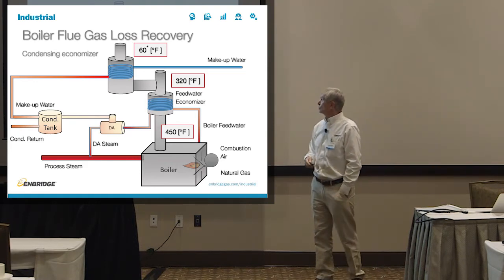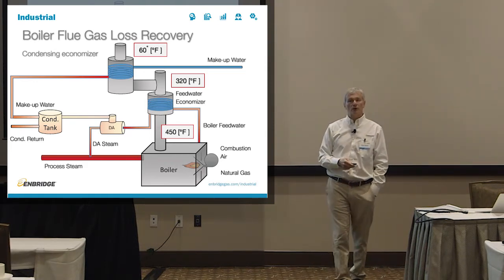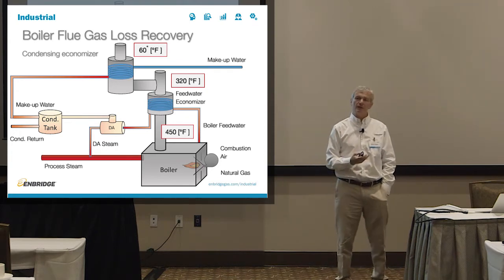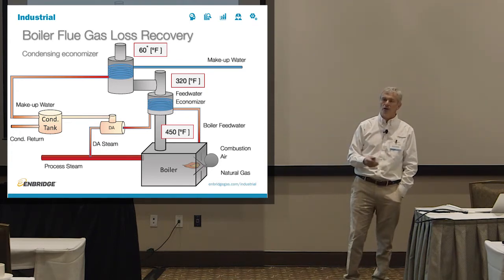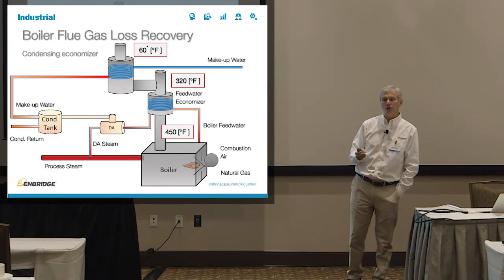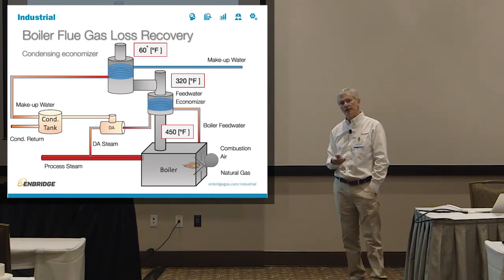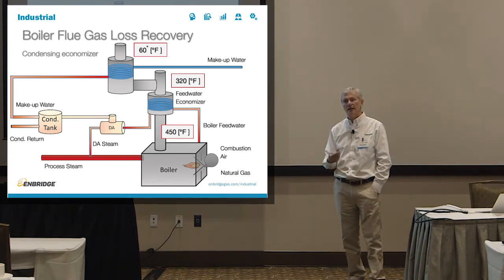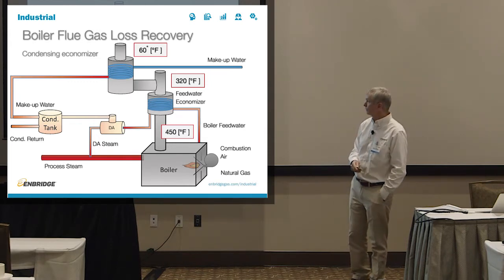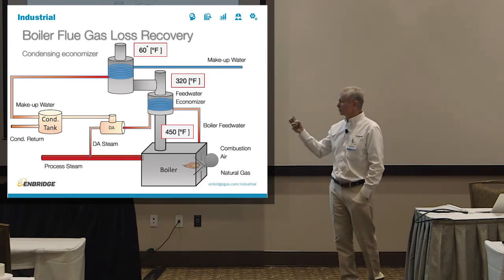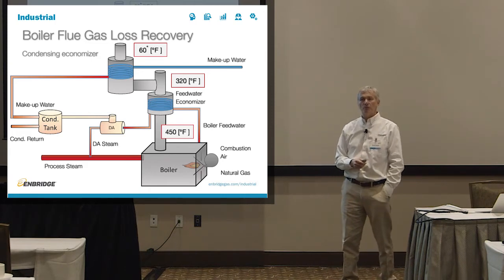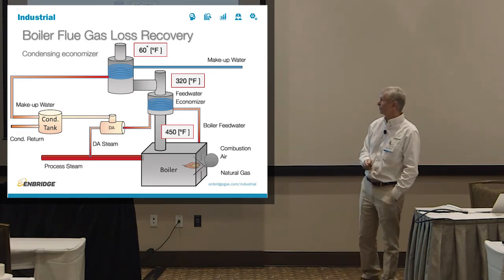Then, of course, you could put makeup water through the condensing economizer directly. You don't have to preheat it. You don't have to take the boiler feed water. You take cold makeup water from the city and put it directly through the condensing economizer because it can handle that low temperature input. And then you can put that stream back into your makeup water stream rather than going directly into the boiler.